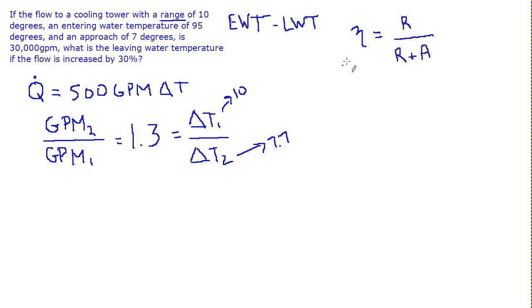The efficiency of a cooling tower is the range divided by the range plus the approach. And now let's separately remind ourselves what those are. Range is entering water temperature minus leaving water temperature.